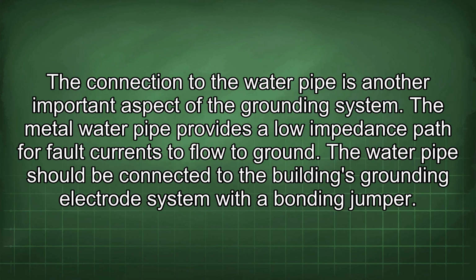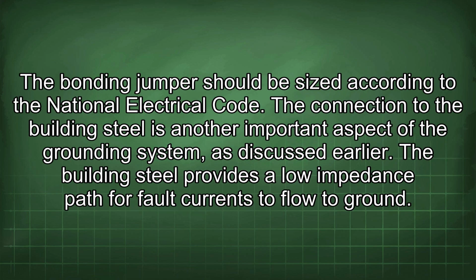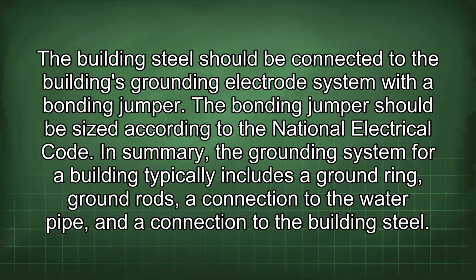The connection to the water pipe is another important aspect of the grounding system. The metal water pipe provides a low impedance path for fault currents to flow to ground. The water pipe should be connected to the building's grounding electrode system with a bonding jumper. The bonding jumper should be sized according to the National Electrical Code. The connection to the building steel is another important aspect of the grounding system, as discussed earlier. The building steel provides a lower impedance path for fault currents to flow to ground. The building steel should be connected to the building's grounding electrode system with a bonding jumper. The bonding jumper should be sized according to the National Electrical Code.